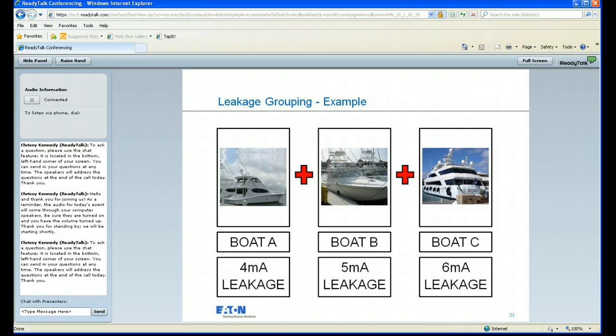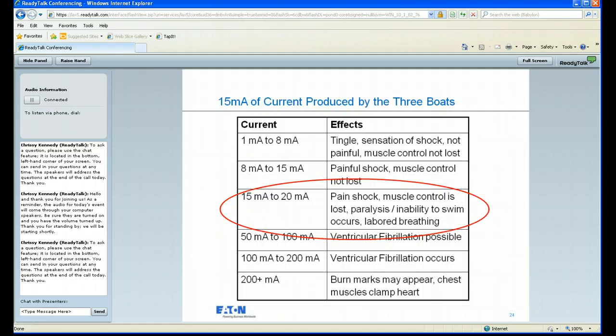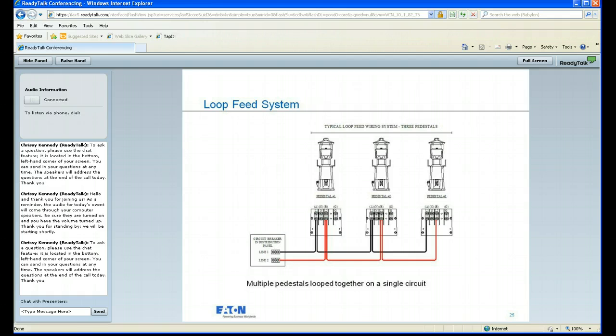As another example here, we've got boat A producing 4 milliamps, boat B producing 5, and boat C producing 6. As a grand total, those boats are producing 15 milliamps. And if we go back to our chart on what a swimmer would see, 15 milliamps is enough to produce pretty damaging results, enough to produce loss of muscle control and the inability to swim, which could lead to unintentional drowning. So that's something to keep in mind when you're taking a look at what system you choose for protection or monitoring. We also discussed the differences in how wiring methods will affect the way you monitor, or how difficult or easy it would be to identify what boats are causing problems.